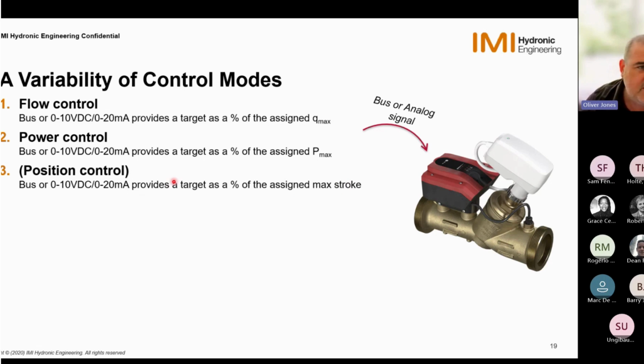And position control, this is something that we probably wouldn't typically see in a commercial aspect or on projects. This gives us a percentage of the assigned maximum stroke available for the valve. This is something that's typically used in-house for testing and things like that, but there is a position control available if need be. Over the top of those, and these can't be placed as a separate item, so we can't control just via DT limitation. We have to overlay this as a secondary control to either flow or power position. And this will control and limit our delta T based on either flow control being the main function or power control being the main control function.